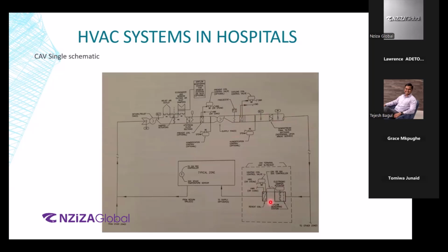But if you are using that same air handler to serve a pre-operative room, a pharmacy area, laboratory area, the design temperatures over there might be a bit different. Okay, it becomes very crucial when it comes to the patient areas. The reason being, the air that is coming in at 15 to 16 degrees, industry standard, or you can correct me if in this part of the world it is something else. 15 to 16 degrees, we are introducing it into the room, right? When we have a patient who is trying to recover, their body heat is already losing at a faster pace. If we introduce that 15-16 degree air into that same area, right, and the outside loads are not countering that cold air, the heat will be transferred from the patient's body, right? Hot to cold.